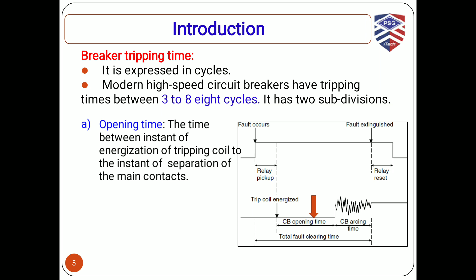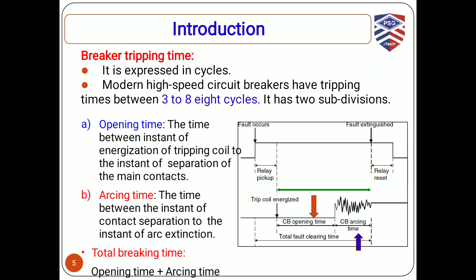The next time is arcing time. It is the time between the instant of contact separation and the instant of arc extinction. So what is the total breaking time or tripping time of the circuit breaker? It is the sum of opening time and arcing time. That again is the sum shown in the figure.